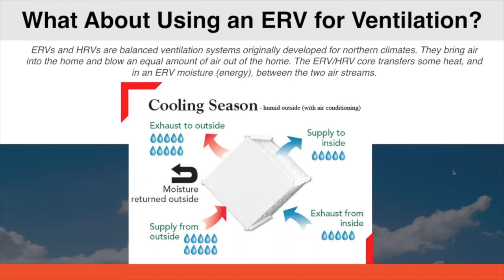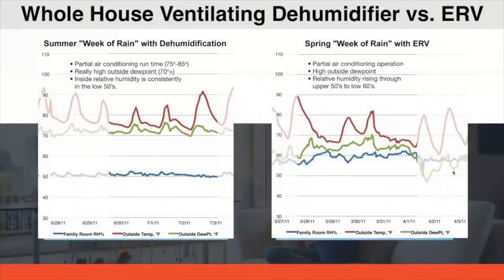So ideally, if customers can afford it, I know that if you watch Matt Reisinger's videos, and Matt is a huge supporter of ours, in his higher end custom homes, if his customers can afford it, he will always put in an ERV and a dedicated dehumidifier. But in his homes where he has to pick one or the other, he will always choose the ventilating dehumidifier over the ERV because, again, the ERV will always contribute to the moisture load. So we did a case study down in Orlando, Florida, with a home, and it had an ERV in it. And you can see here on the right side where it says spring week with an ERV.